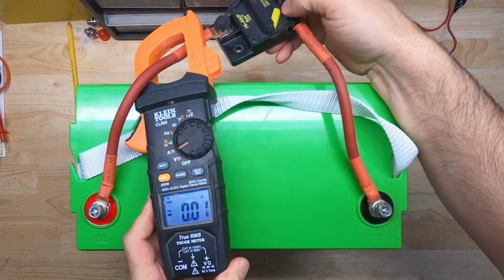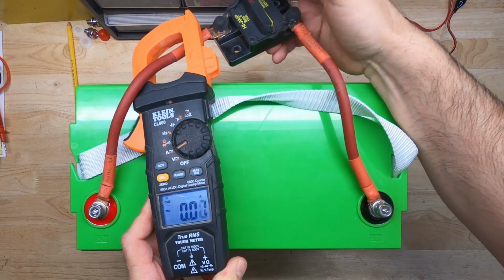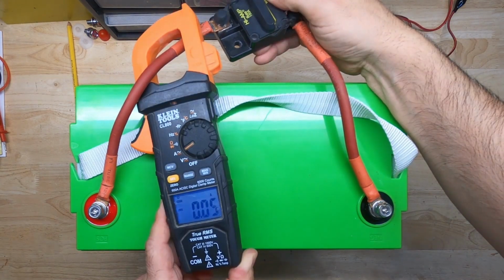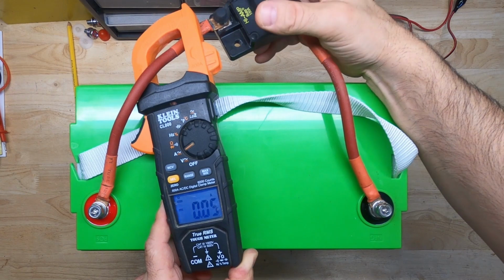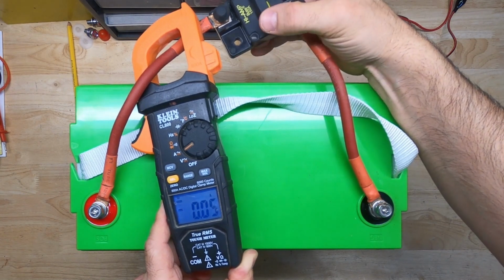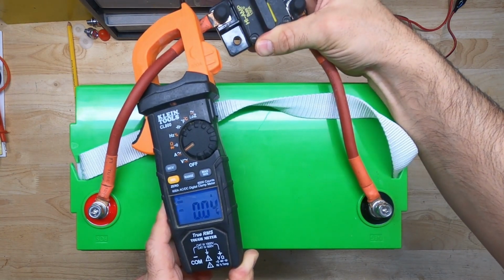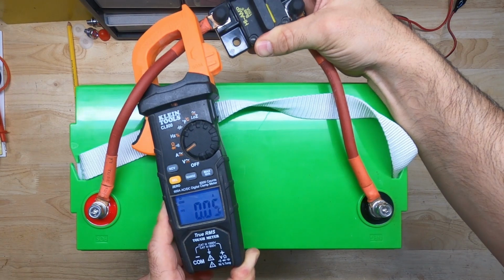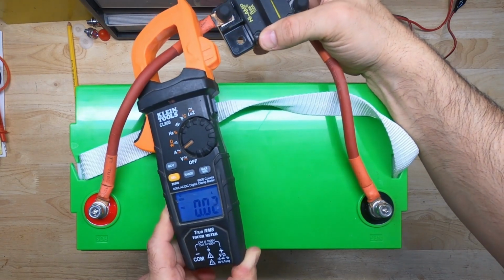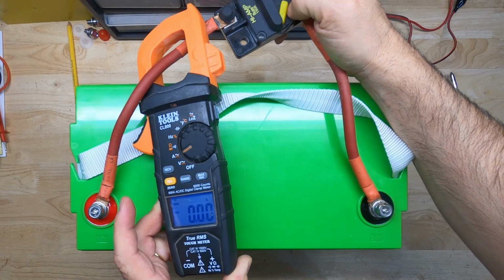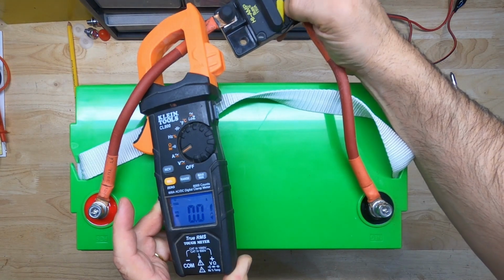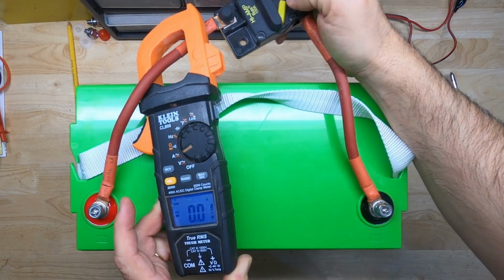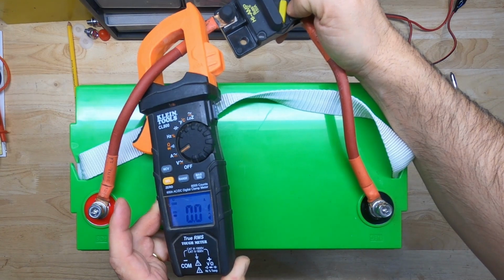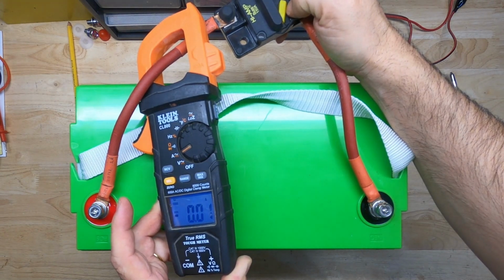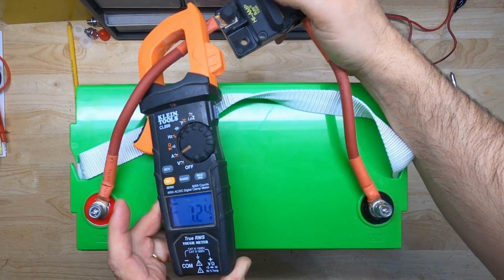So here we go, we're going to flip the breaker. So if it was continually supplying current through the BMS, through the breaker, this breaker would be hot by now, and it would have already tripped. So we can see the BMS is shutting off. I can't say that there's an actual delay in which it turns back on automatically. It just basically stays off as long as the short condition exists.